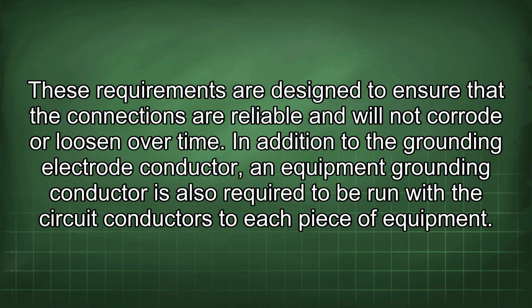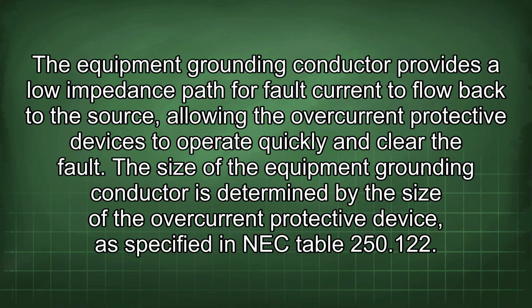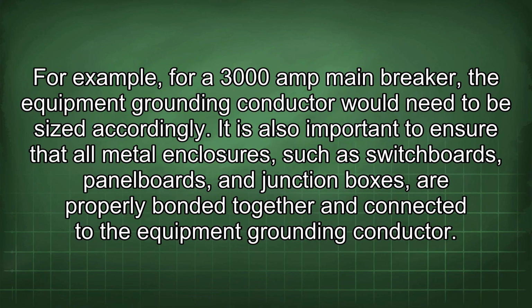In addition to the grounding electrode conductor, an equipment grounding conductor is also required to be run with the circuit conductors to each piece of equipment. The equipment grounding conductor provides a low impedance path for fault current to flow back to the source, allowing the overcurrent protective devices to operate quickly and clear the fault. The size of the equipment grounding conductor is determined by the size of the overcurrent protective device, as specified in NEC Table 250.122. For example, for a 3000 amp main breaker, the equipment grounding conductor would need to be sized accordingly. It is also important to ensure that all metal enclosures, such as switchboards, panel boards, and junction boxes, are properly bonded together and connected to the equipment grounding conductor.